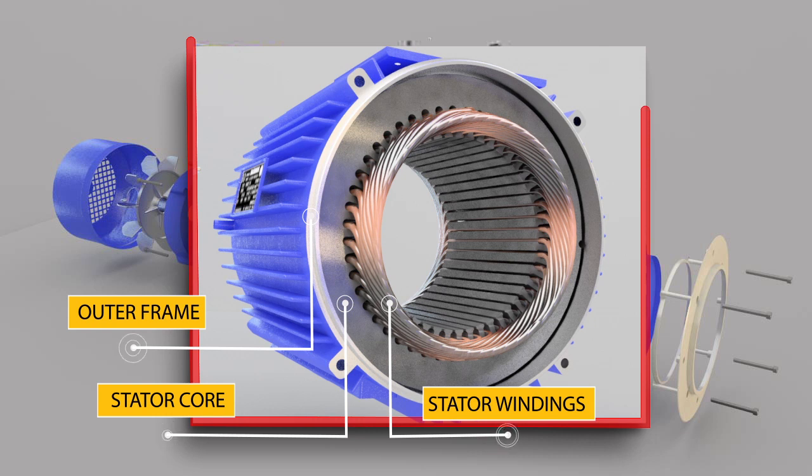The core of the stator carries three phase windings which are usually supplied from a three phase supply system. The six terminals of the windings, two of each phase, are connected in the terminal box of the machine. The stator of the motor is wound for a definite number of poles, depending on the speed of the motor. If the number of poles is greater, the speed of the motor will be less and if the number of poles is less, then the speed will be high.